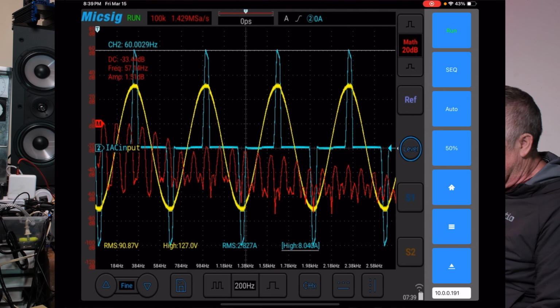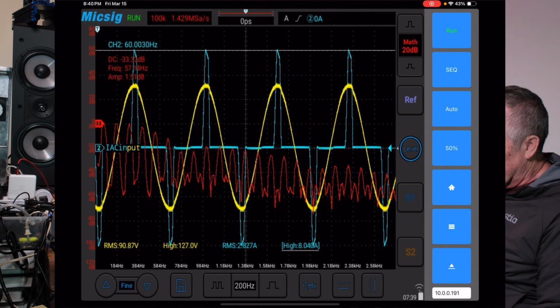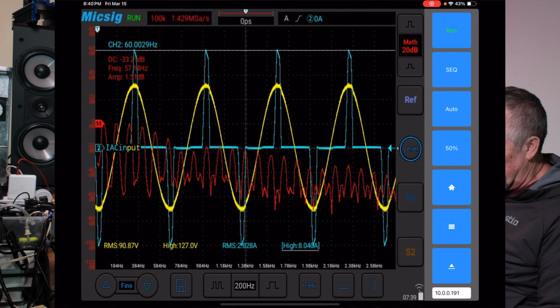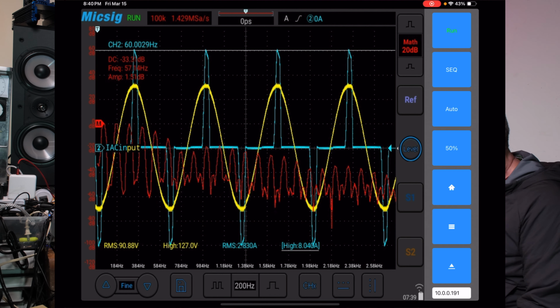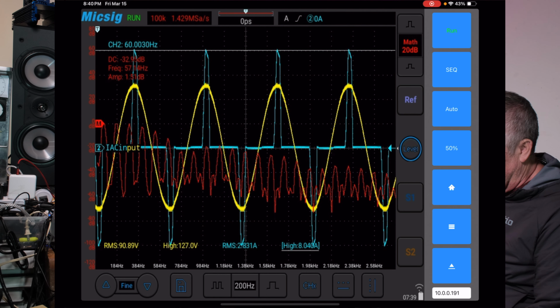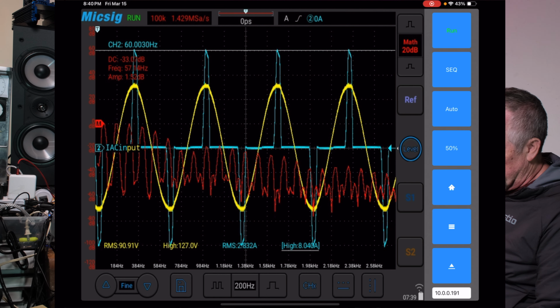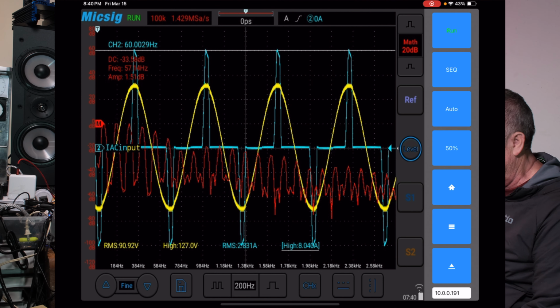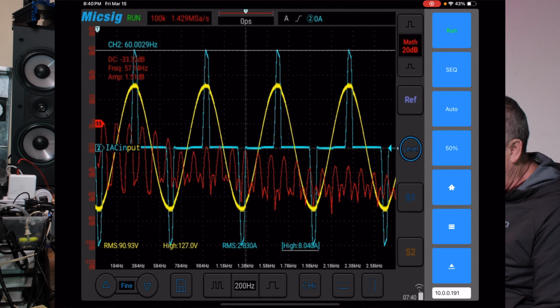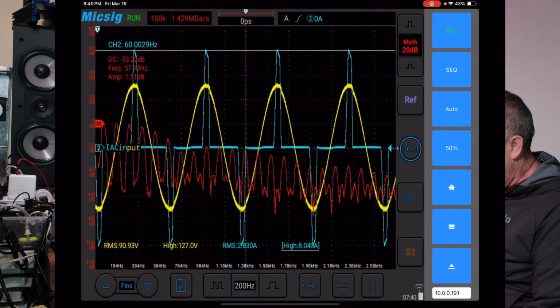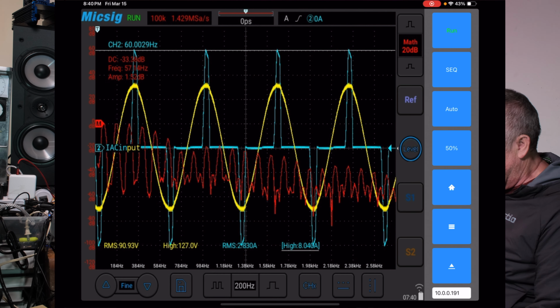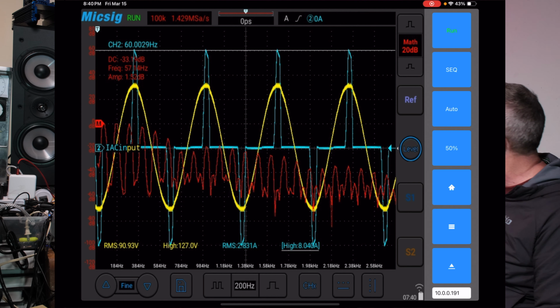So it's not like the voltage, where most of it is the fundamental plus some harmonics. Here the 60 hertz amplitude is equal to the second and third harmonic, the fourth drops off a little, the fifth a bit more, the sixth a bit more, and by the seventh or eighth harmonic it's dropped off about 20 dBs. So that's very dirty power, okay? That's what it looks like at the input to the transformer.